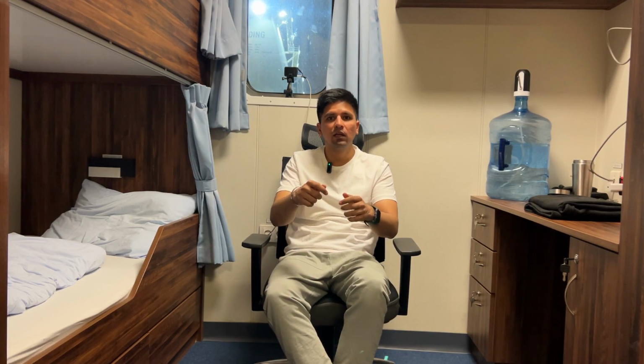Because on the electrical side, you will learn how to test the alarms. Sometimes the level sensor is ultrasonic or electronic, so you need to swap the wires or something to simulate the alarms, to check whether when we give the fault, the Kongsberg system, your alarm and monitoring system, or your mimics, your computer simulation gives you an alarm—because everything works with computer simulation.